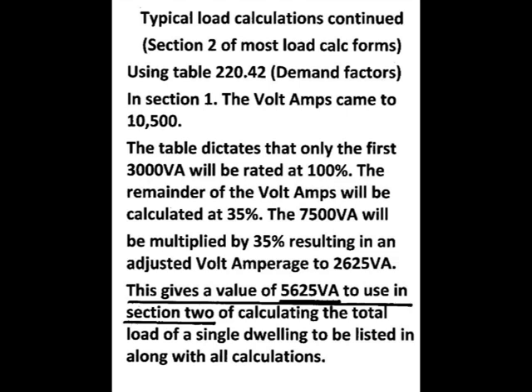Going to section 2, using table 220.42 demand factors — in section 1 the volt amps came to 10,500. The table dictates that only the first 3,000 volt amps will be rated at 100%. The remainder of the volt amps will be calculated at 35% — that's very low. The 7,500 volt amps will be multiplied by 35%, resulting in an adjusted volt amperage of 2,625 volt amps. This gives you a total value of 5,625 volt amps to use in section 2 of coming up with the total.